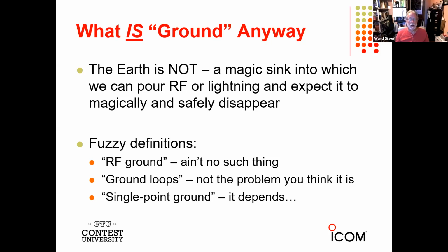The other is single point ground. It depends, as we'll talk about in a minute. Single point means many different things. A single point means a very different thing to the AC electrician, where the frequency is 60 hertz and the wavelength is about 5 million meters, and it means a lot different to the RF guy operating at 10 meters, where the wavelength is 10 meters. Imagine that. And so you have very different perspectives on things. So when you say these things like single point ground, you have to make sure you qualify it.